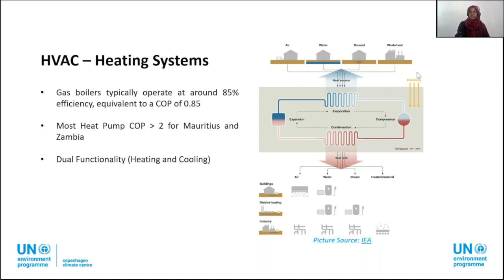And that brings us to something called COP, or coefficient of performance. COP is a way to measure how efficient a system is. A gas boiler, for example, has a COP of about 0.85 to 0.9, meaning that for every 1 unit of energy it uses, you get about 0.85 unit of heat. But a heat pump, because it's just moving heat rather than creating it, can have a COP of 3 or even 4. So for every unit of electricity it uses, you get 3 to 4 units of heat.